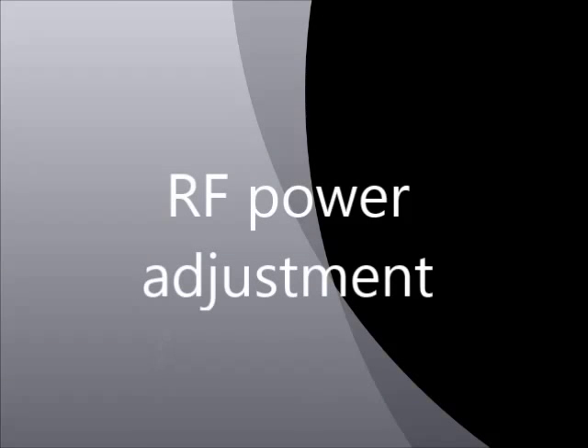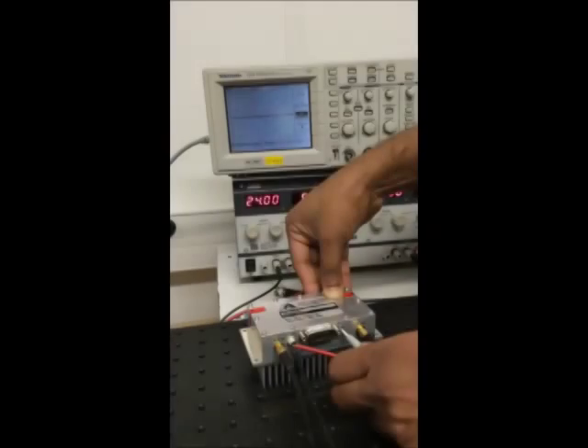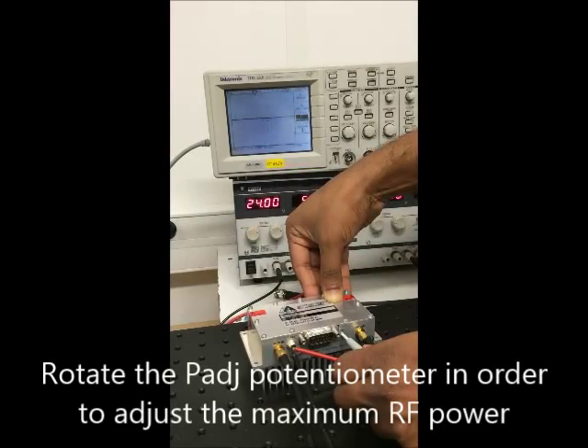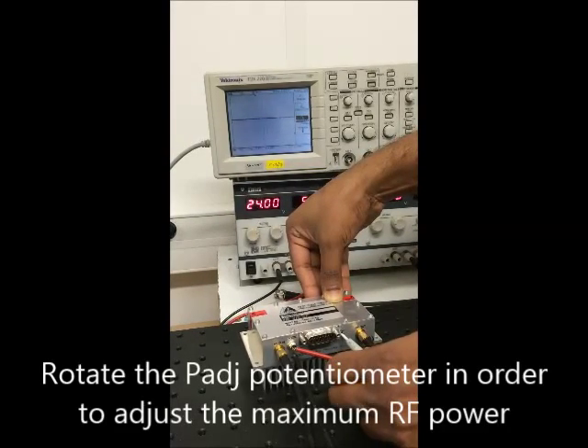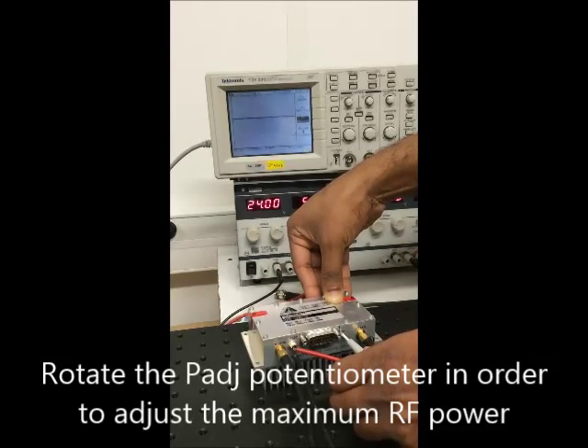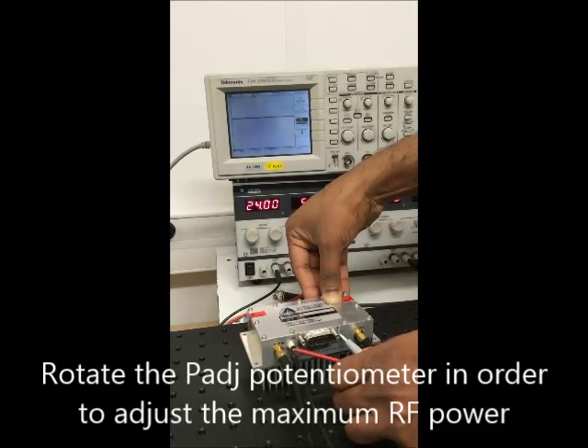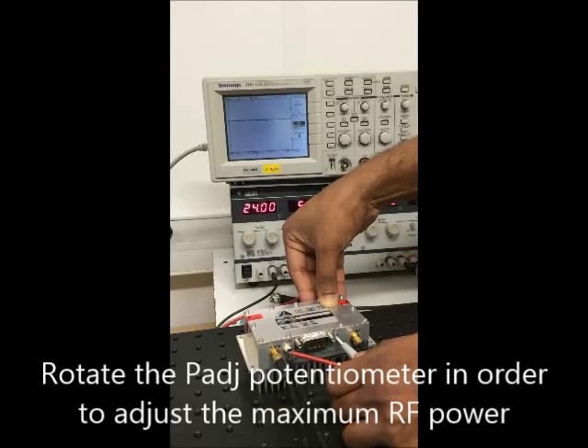Radio frequency power adjustment. With a screwdriver, turn the power potentiometer located on the front panel of the driver, and optimize power level to get best efficiency.